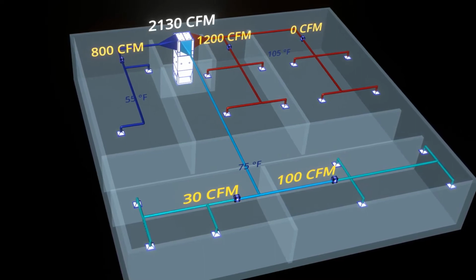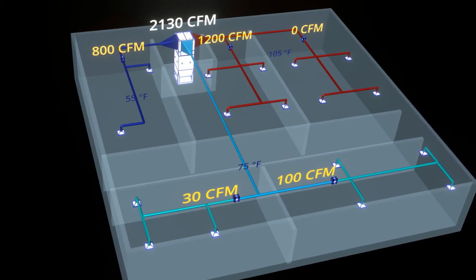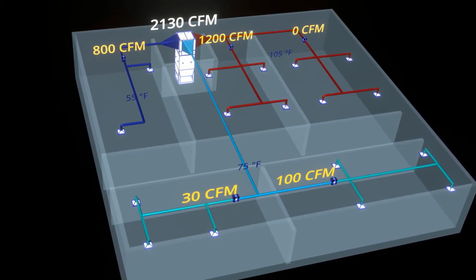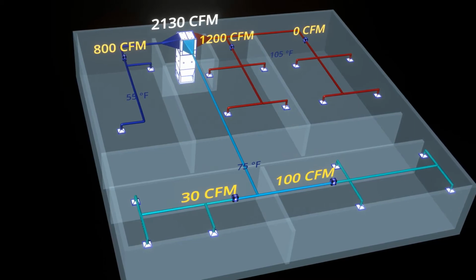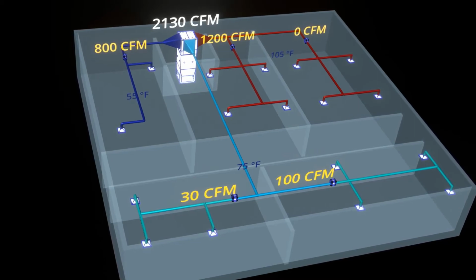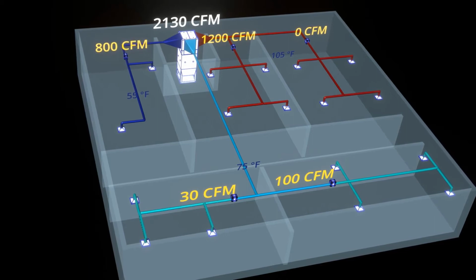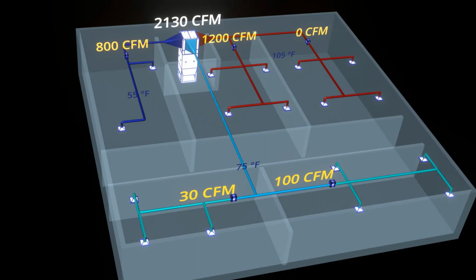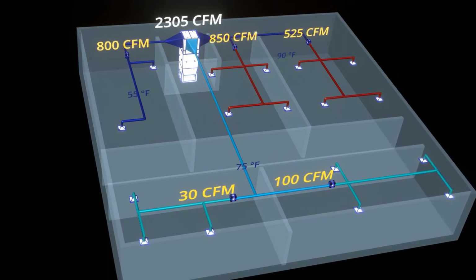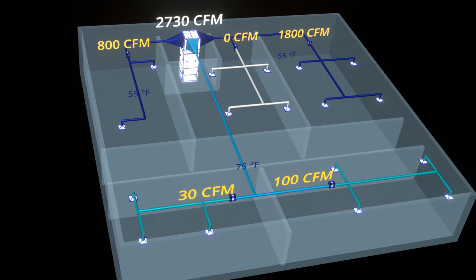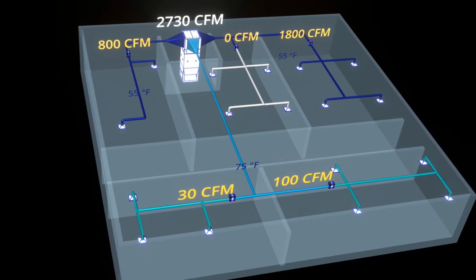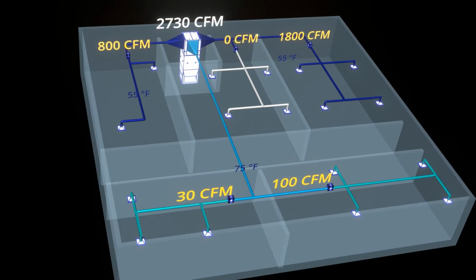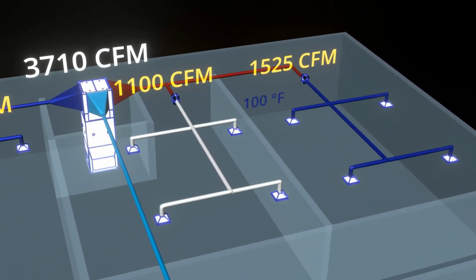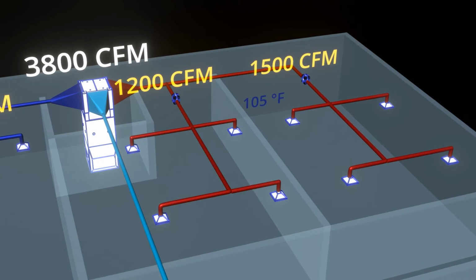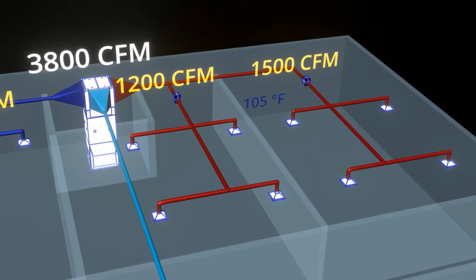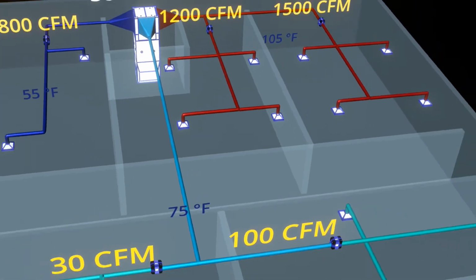The AirCube 2, 3, and 4-sided coil configuration provides independent zoning and on-demand multiple temperature zones, which leads to lower energy usage and eliminates complex and expensive zone coil and hydronic infrastructure systems, while still providing the required temperature to zones simultaneously. With the high turndown SAVs and our multiplexing air handling algorithm, different temperatures can be supplied to the same zone simultaneously from the same air handling unit. The high turndown precision flow measurement of the smart air valves meets the zone temperature set points with the exact amount of pulses of hot and cold air.